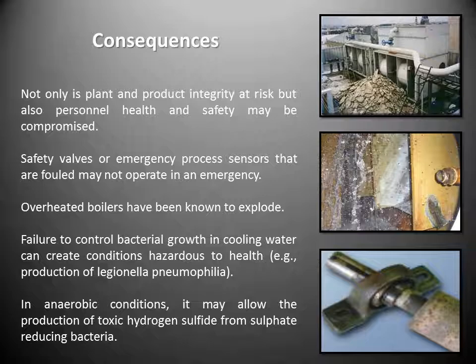Failure to control bacterial growth in cooling water can create conditions hazardous to health, such as the production of mold and bacteria like Legionella pneumophila, which is commonly found in cooling towers. In anaerobic conditions, it may allow the production of toxic hydrogen sulfide from sulfate-reducing bacteria.